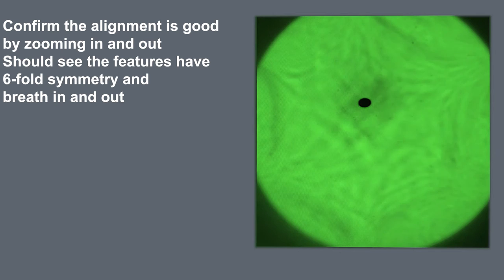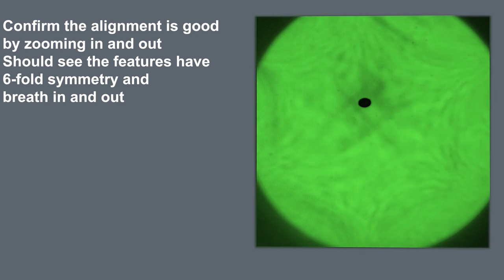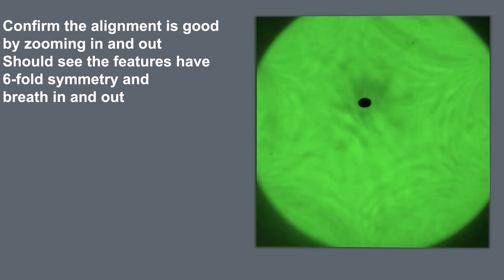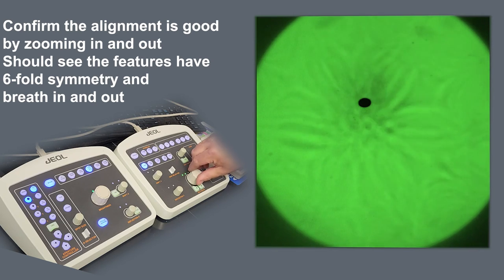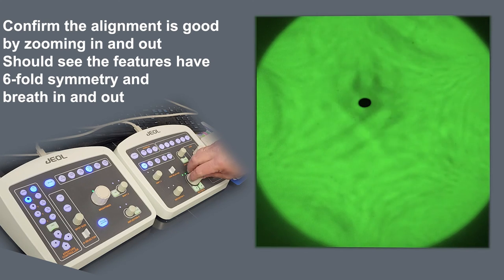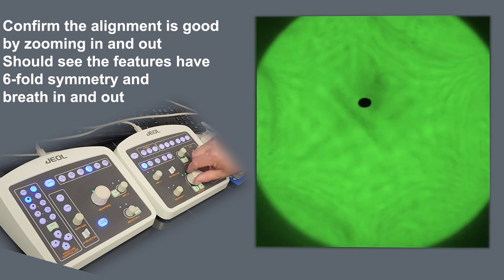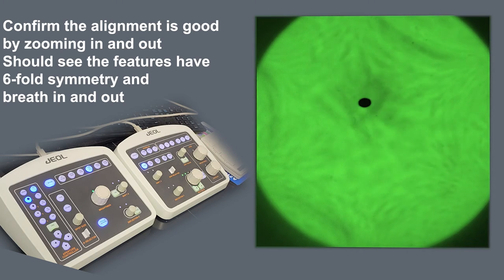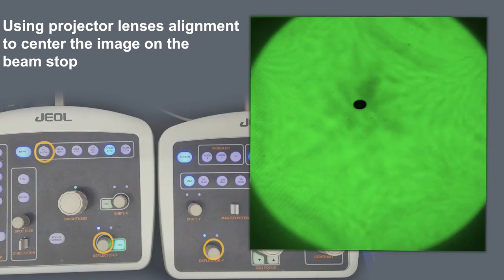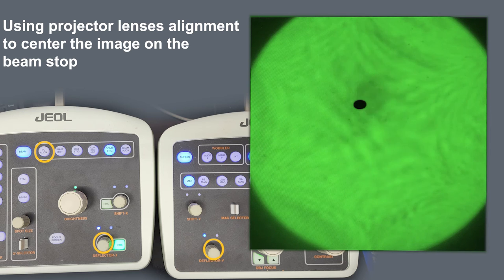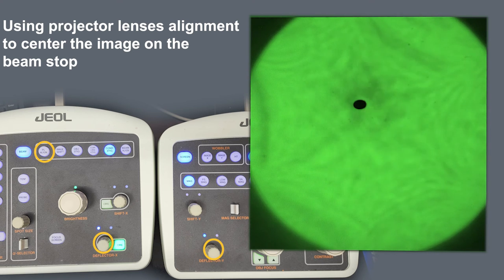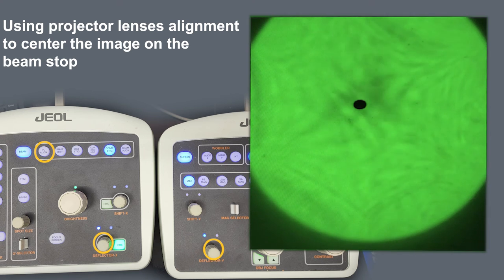The correction is done when you see a homogeneous and uniform blurry area in the center of a six-fold symmetry star-shaped image on both sides of the focus point, namely underfocus and overfocus. Center the ronchigram image on the focus screen using PL align and deflector X and Y.